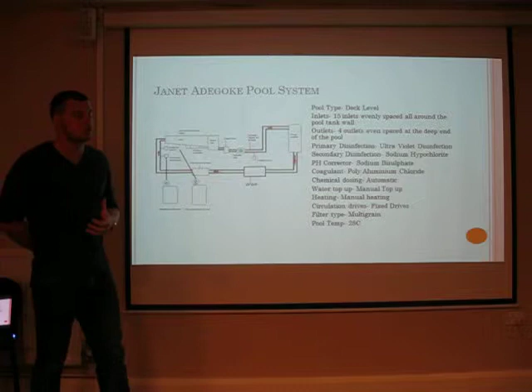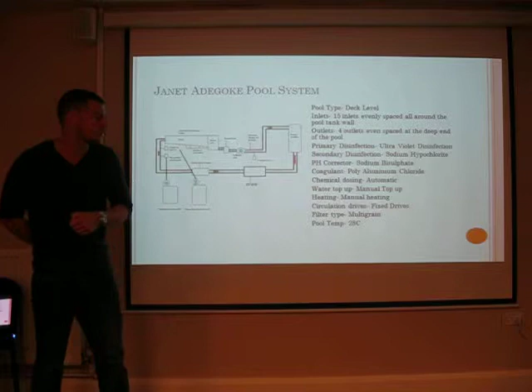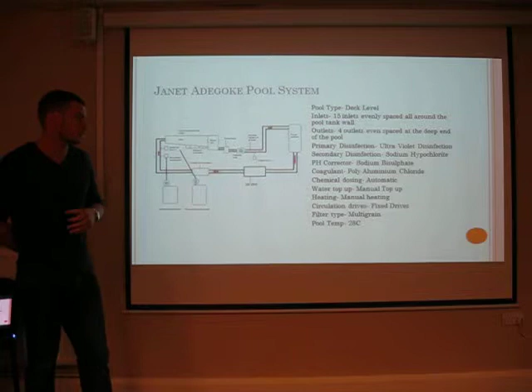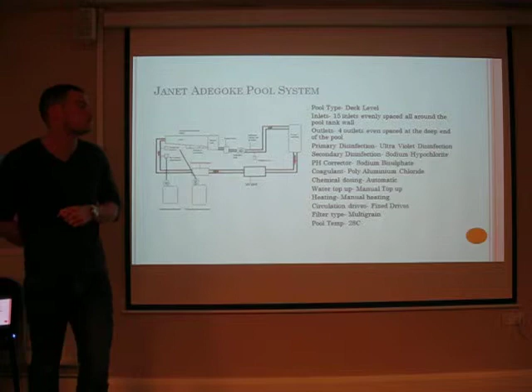The primary disinfection uses a more up-to-date ultraviolet unit, with secondary disinfection being sodium hypochlorite as backup. The pH corrector is sodium bisulfate, and they use PAC, same as Dormers Wells. The chemical dosing unit is automatic, same as Dormers Wells, but water heating is manual rather than automatic. Circulation drives are fixed rather than variable. They have the same multi-grain filter type, and the pool temperature is kept at 28 degrees Celsius.